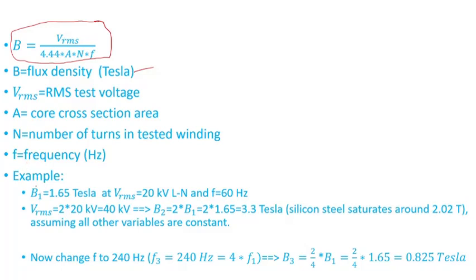Here's an example. Let's assume if you apply a voltage of 20 kV line-to-neutral and the frequency is 60 Hertz, the calculated flux density is 1.65 Tesla. Now, if you increase the voltage—like I was saying here for distribution...